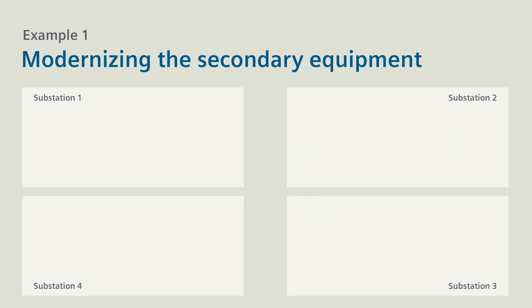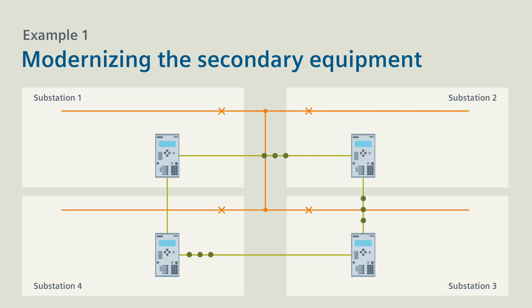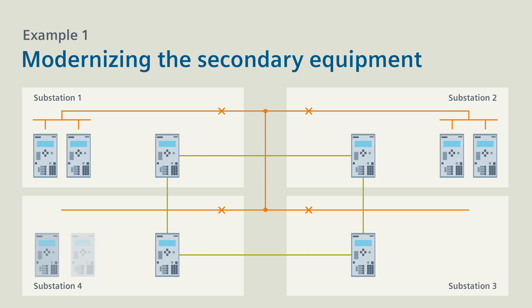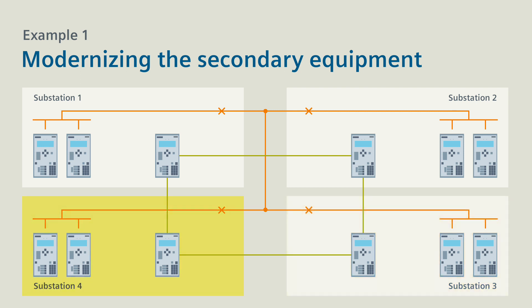Example 1 shows four substations with SIPROTEC 4 line protection devices that communicate in a ring. Further SIPROTEC 4 devices protect the remaining fields of the individual substations. Gradually modernizing the secondary equipment shown here is now quite easy. De-energize the line field in substation 1 and log off the line protection device.